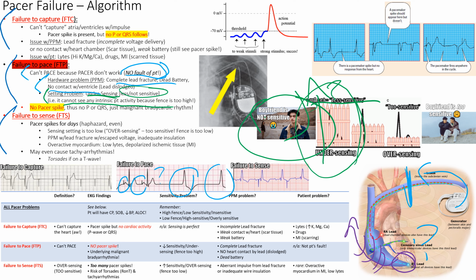And that would be failure to pace. So that fence is all the way up there. It's not going to pace because of a setting that we set on the pacemaker itself. We set the sensitivity way too what? Low or high? We set the sensitivity way too low, to the point where they don't care at all. You can think of it as like caring.